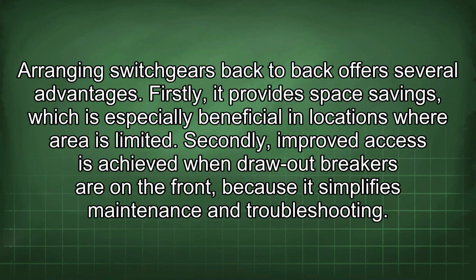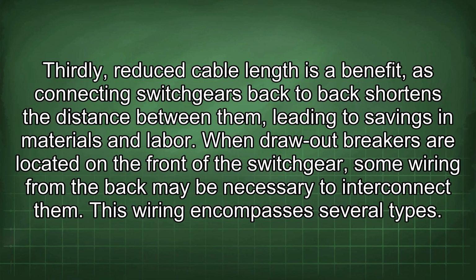Arranging switchgears back-to-back offers several advantages. Firstly, it provides space savings, which is especially beneficial in locations where area is limited. Secondly, improved access is achieved when draw-out breakers are on the front because it simplifies maintenance and troubleshooting.